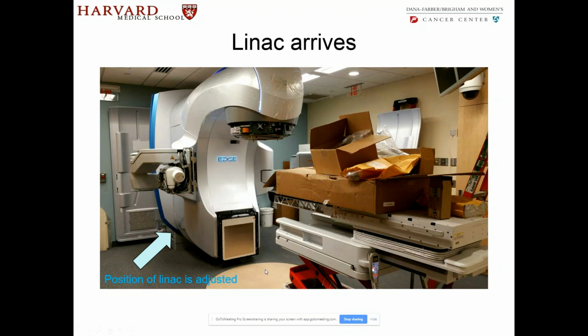The couch is placed, and the ISO center is very carefully placed for the couch. The Linac is then brought in place, and this is the end where they have this hydraulic press through which they can shift it by millimeters, and the Linac is moved and adjusted so that its ISO center matches the ISO center of the couch. If the couch goes out of spec, it's a huge deal to put it back in place. It's almost impossible to do it.